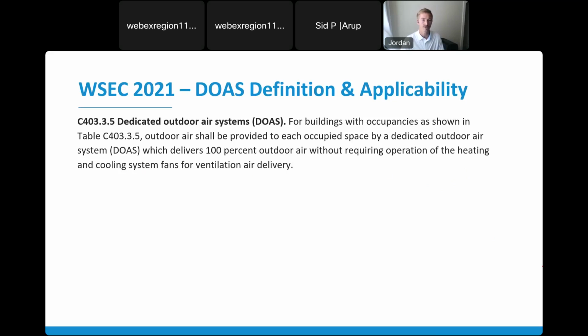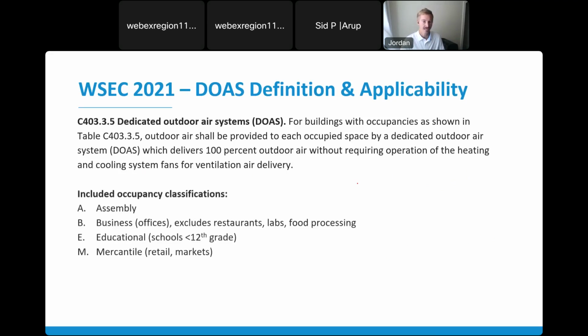Section C403.3.5: for buildings with occupancies as shown in this table, outdoor air shall be provided to each occupied space with a DOAS, which delivers 100% outside air without requiring operation of the heating and cooling system fans for ventilation air delivery. That table includes almost all assembly occupancy types, businesses, which of course includes offices and professional services, but notably excludes restaurants, labs, and food processing. All educational schools under 12th grade, so not including higher ed. And then the M group, which is mercantile, includes retail, markets, department stores, etc.